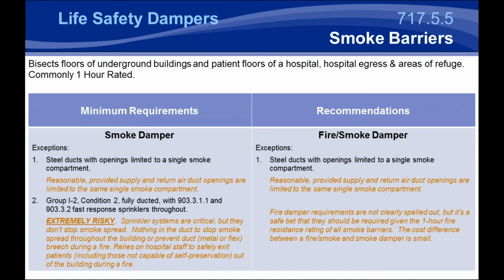That's no longer allowed and hasn't been allowed for quite some time. All smoke dampers have to come from a factory after being tested for operation and are factory wired to fully open and close and are correctly mounted. So right now, there's really not that type of maintenance issue or nuisance issue that's associated with smoke dampers. But unfortunately, they were very successful while also relying on the training of their staff and the sprinkler systems to allow the removal of that smoke damper requirement.